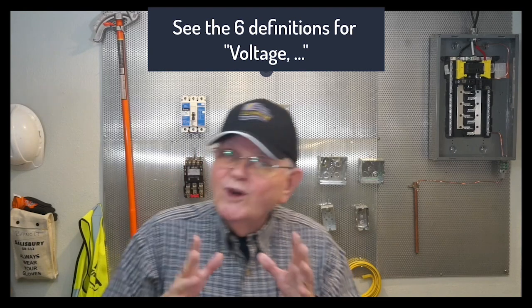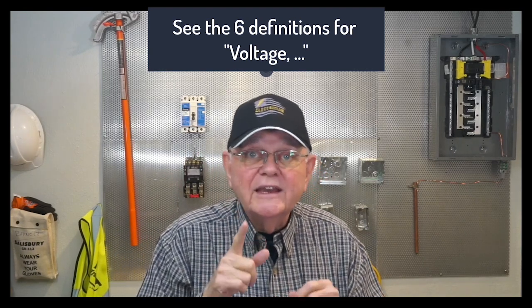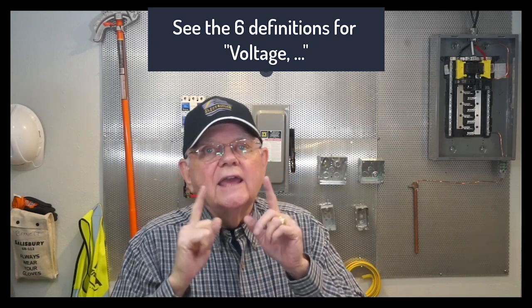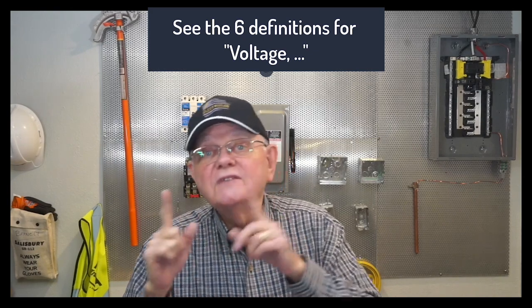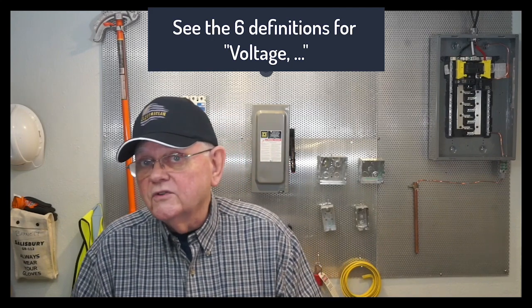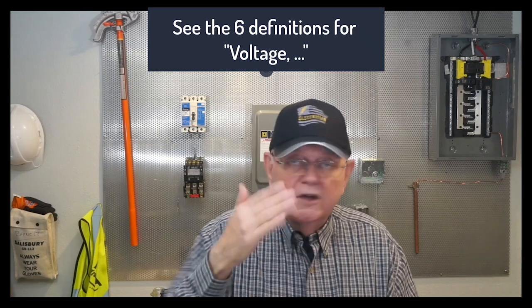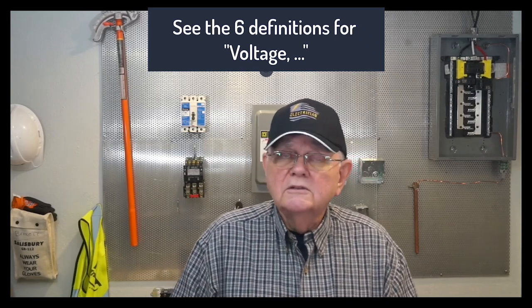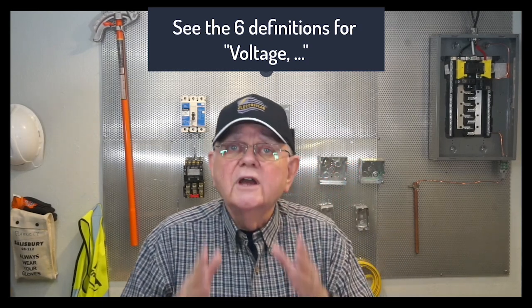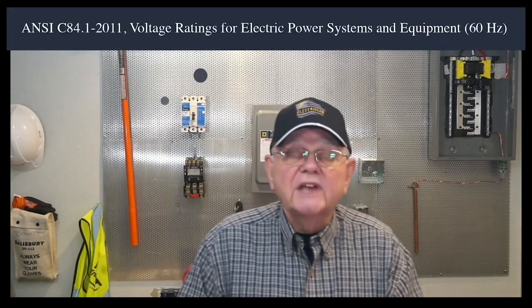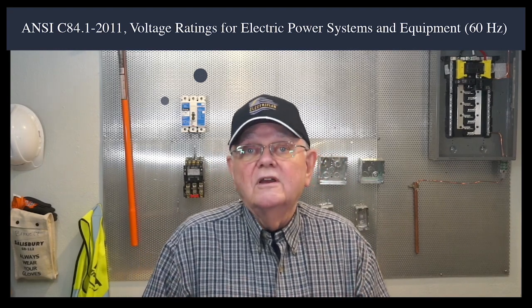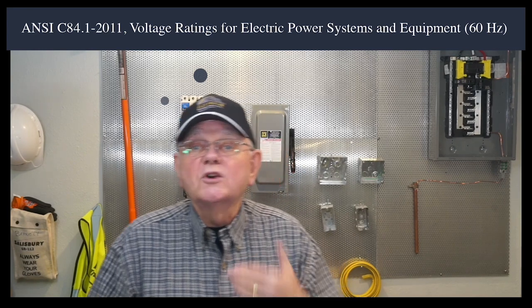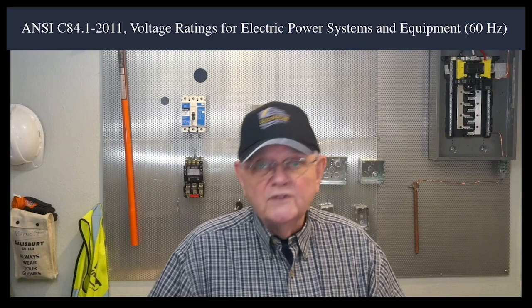Now, low voltage is also defined in the code. However, you got to be careful. It says low voltage is 24 volts. However, it only applies to Article 551 for recreational vehicles. So I can't go around throughout the code and say, oh, well, the code says 24 volts is low volts. No, it doesn't. It doesn't say that at all. In Article 551, low voltage is 24 volts. It's interesting if you look up nominal voltage, and it gives the definition, the voltage assigned to a system. And then there's an informational note, and it's going to refer you to an ANSI IEEE standard, the C84.1 standard, which is the voltage ratings for electric power systems and equipment. So that's where we go to actually find the voltage classifications on our system.